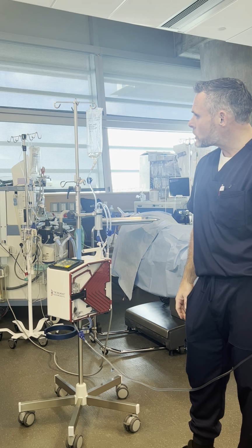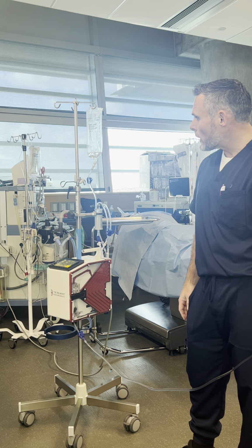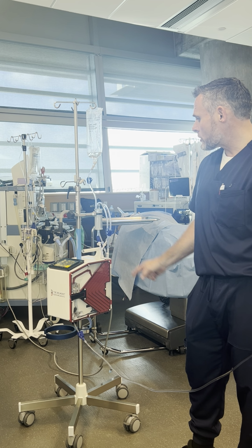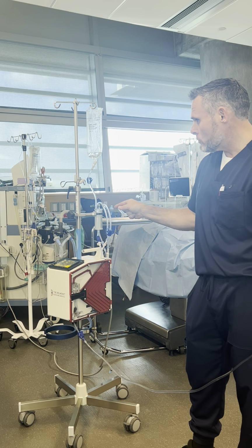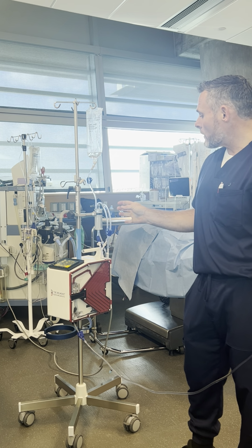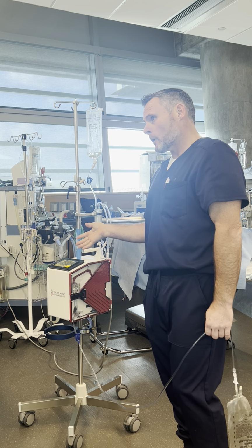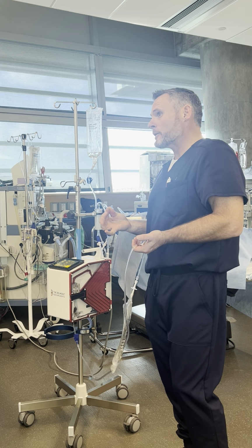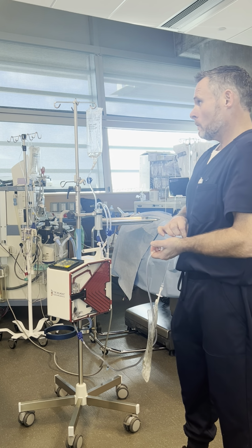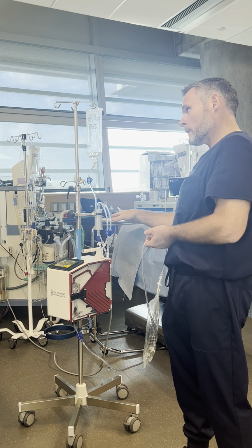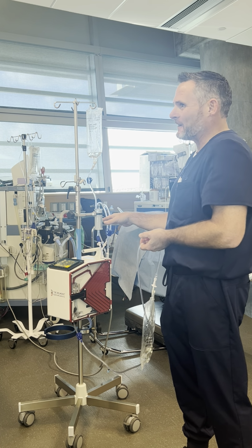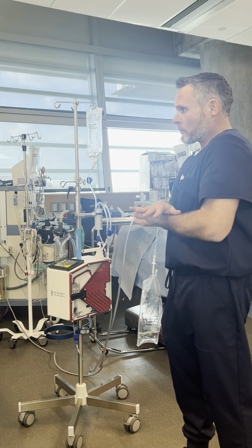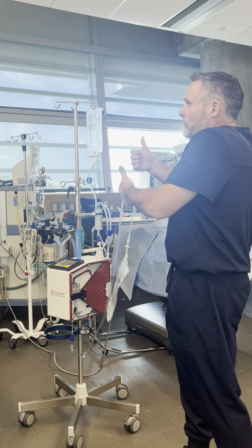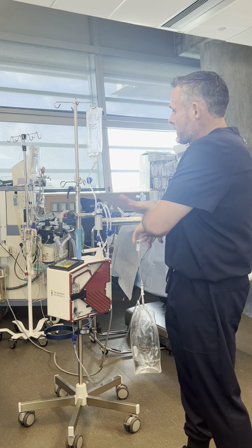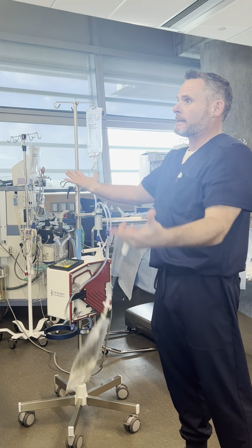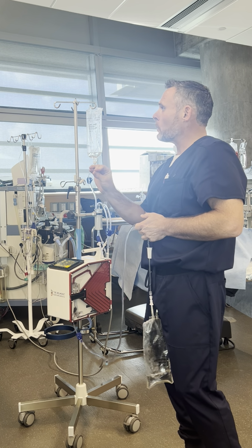I was using a long, skinny straw, and I hit max flow rate, and that straw was saying, that's too much. That's too much flow rate, too much shake, too much blood. And that distal port, the Belmont has a safety mechanism, because when do lines blow? Do y'all know? Lines will infiltrate and break at 350 mercury. That's when you have a problem. You kill somebody. So the machine will not allow you to exceed that. It has a hard stop if it senses that pressure being exceeded. So what happened was that I blew up that mercury. I filled that bag all the way to its top, and it was saying no mas. So when I hit stop, I released it. And then I jogged up with that nice tempo to 120 per minute, and we saved his life.